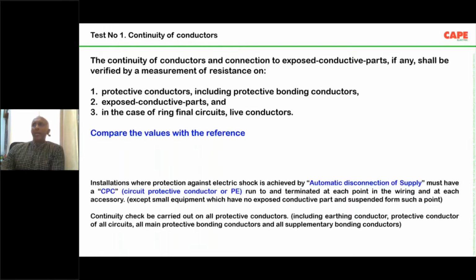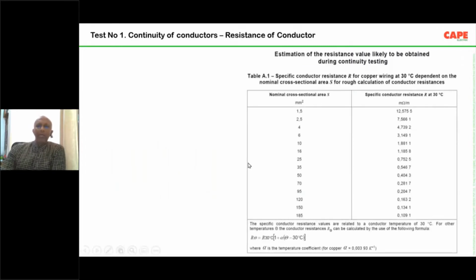Then what is the reference? Imagine in your room or in your facility, you have an MCB distribution board, and you have a circuit consisting of a phase conductor, let us say 25 meters, and a neutral conductor of 25 meters. So your total conductor length is 25 plus 25, 50 meters. If we measure the resistance of the conductor, we are supposed to get a value, and that particular value is provided in the IEC standard. Let us say, for example, a 2.5 square mm wire. The reference value is 7.5661 milli ohm per meter. This is the resistance of the conductor allowed in electrical wiring, and this is the value used worldwide.